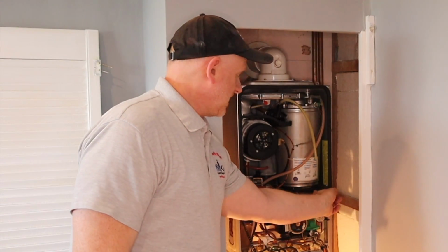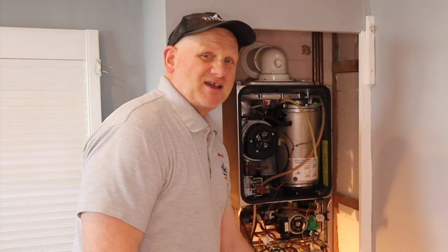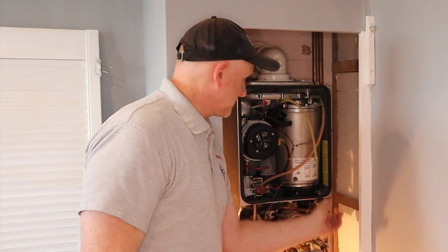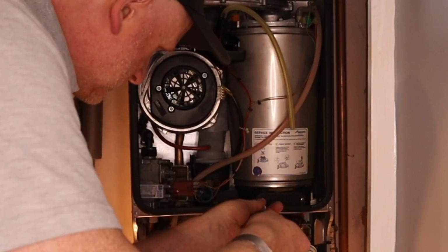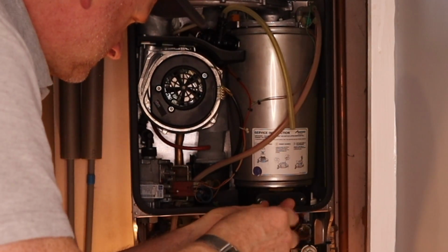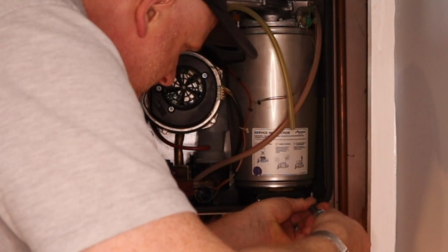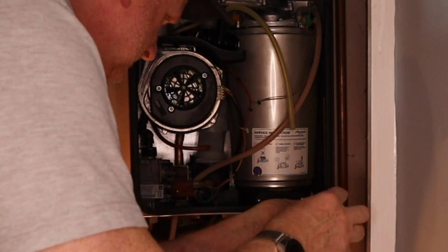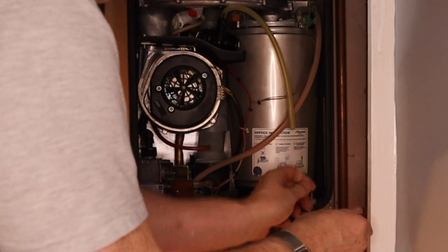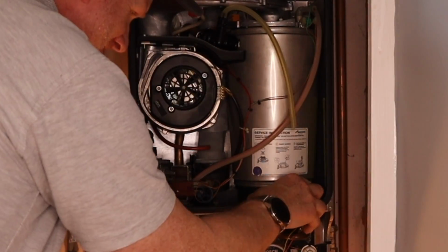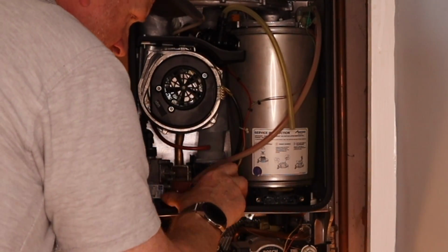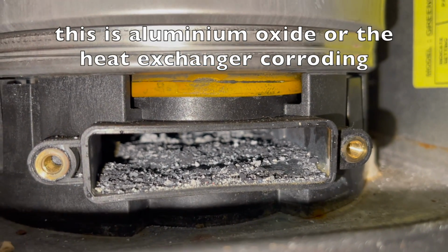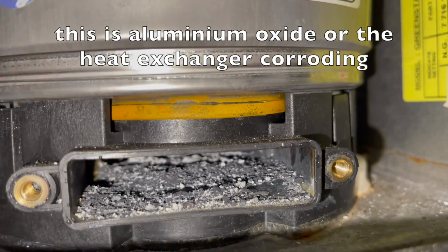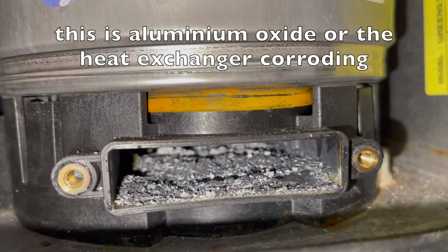Now, first thing I'm going to check is the sump down here to see if there's any debris in there and when the last time this boiler was serviced, because this will be a big telltale sign to see whether it's been serviced recently. There you go. You can see there's quite a bit of debris in there. So that's a bit worrying that this hasn't been serviced in a long time. So we've got to get all that out now.